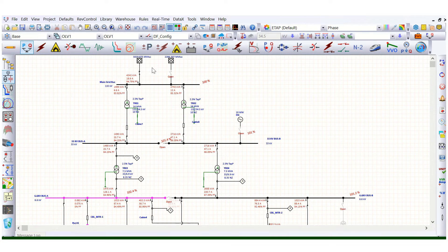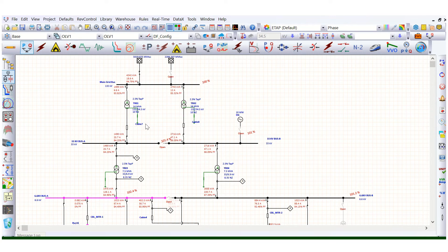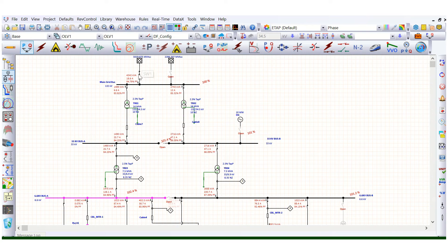Let's say as per client-provided inputs, you have real data that 200 megawatt power is being consumed by this utility system. But as per the simulation output report, almost 300 megawatt power is being drawn. So this network is actually consuming 200 megawatt, but the simulation is showing 300 megawatt. In that case, we need to apply the load diversity factor.